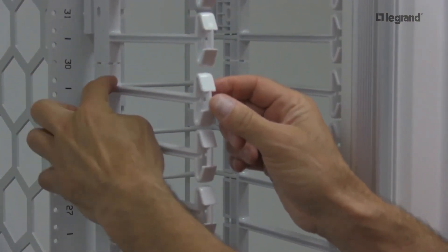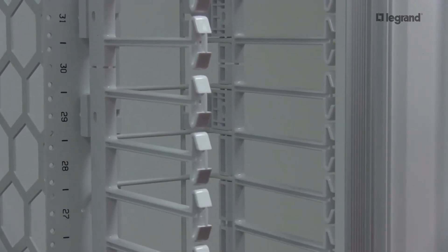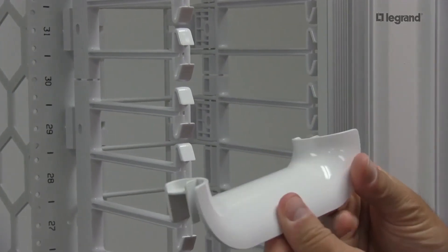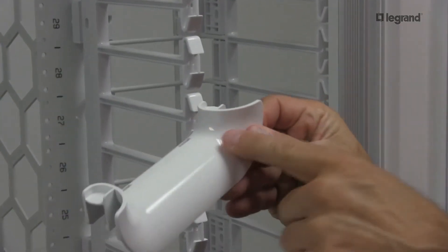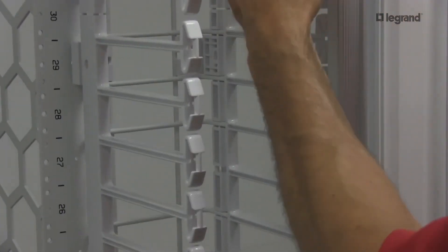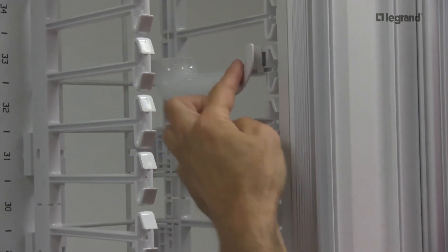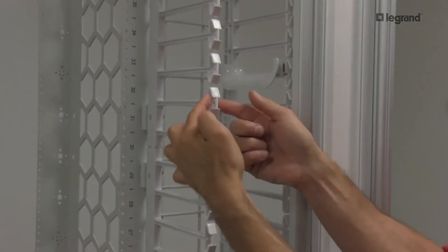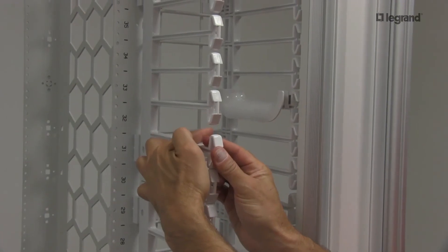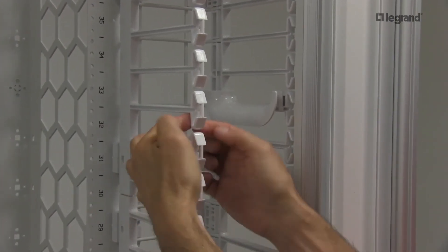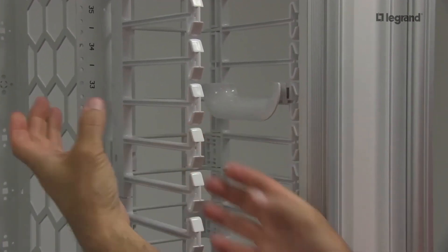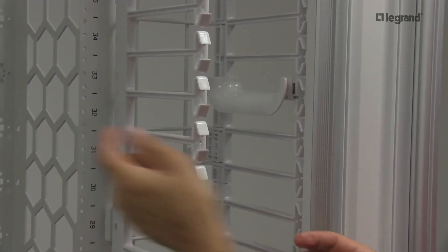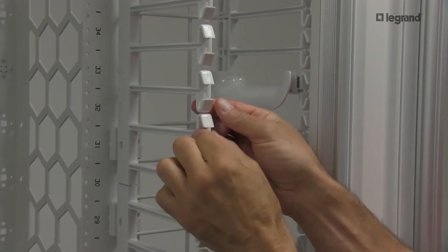The I-beam design also provides more strength at the back and allows us to snap these bend limiting clips, which provide 180 degrees of fiber bend limiting, onto those fingers. There's no chance of crimping fiber because we brought that up 180 degrees. The Legrand patented arrowhead design allows cables to enter this passageway but not come back out due to the stopper on the back. Multiple cable bundles come through here for each RU increment.